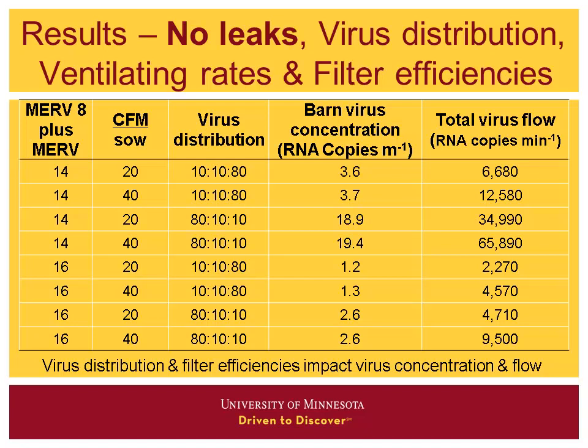With no leaks — everything going through the filters — this shows the comparison between MERV 8 plus MERV 14 and MERV 8 plus MERV 16 at different ventilation rates and distributions. Probably the biggest thing to observe is that with MERV 14 and an 80-10-10 distribution, we're in the 30 to 60 RNA copies per minute range, with concentrations near 19. Whereas with a MERV 8 plus MERV 16 system, concentrations drop to 1 to 2.5, and virus flows are in the 2,000 to 9,000 level.